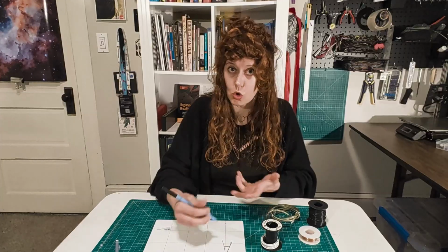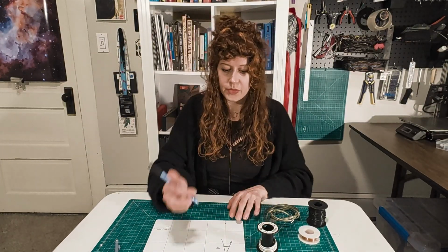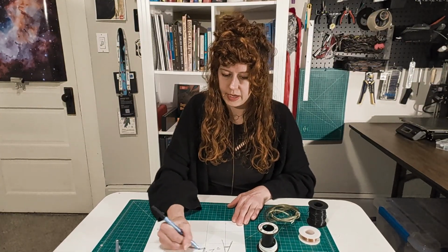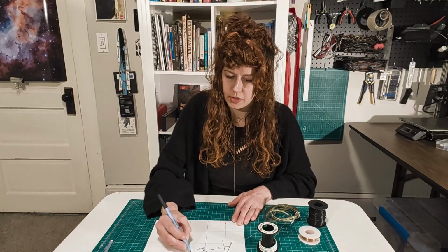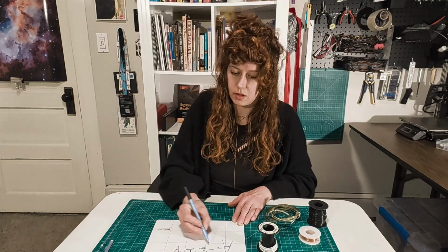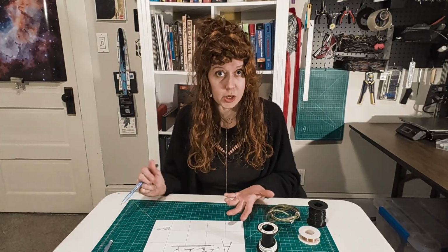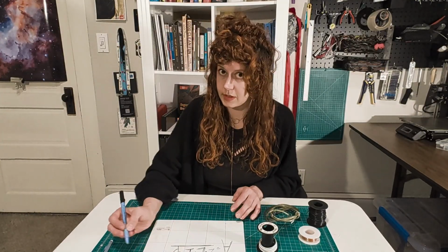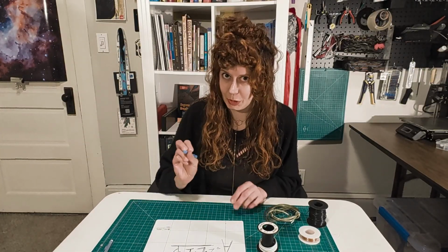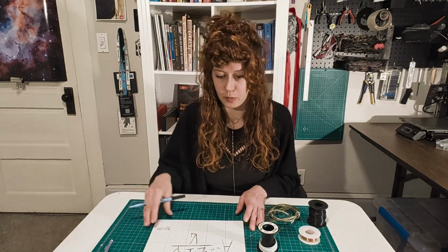So we want to know what is the cross-sectional area of the wire, or how thick is our wire. And so we're going to say area equals 2 times the length of the wire times the current that you are running through that wire times the resistivity of the wire material, which is going to depend on what type of wire you're using. Most of us are using copper, and so I wrote the resistivity in small numbers at the top. We don't have to memorize these things; we can look them up. And then we divide that by the maximum voltage drop that we need for our components.